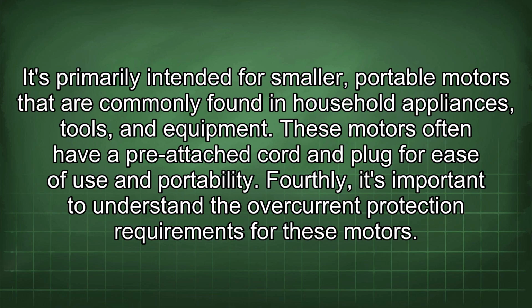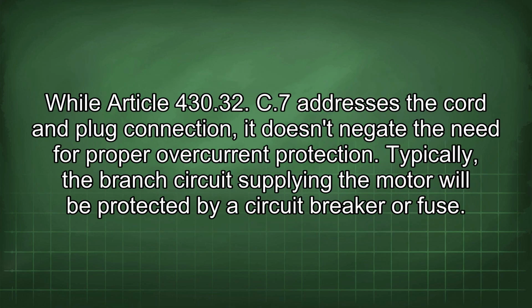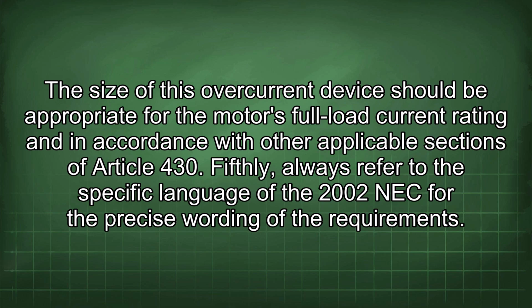Fourthly, it's important to understand the overcurrent protection requirements for these motors. While Article 430.32 C.7 addresses the cord and plug connection, it doesn't negate the need for proper overcurrent protection. Typically, the branch circuit supplying the motor will be protected by a circuit breaker or fuse. The size of this overcurrent device should be appropriate for the motor's full load current rating and in accordance with other applicable sections of Article 430.